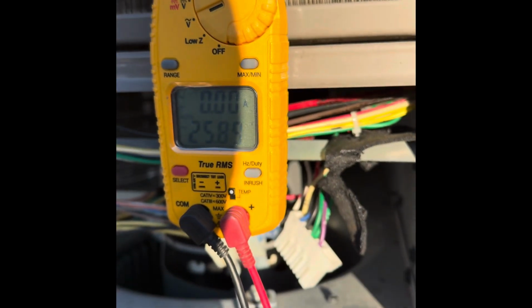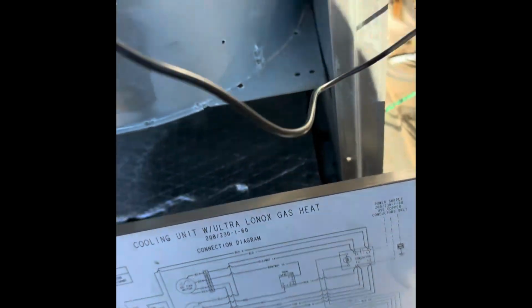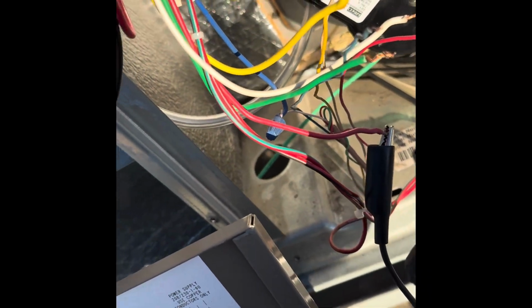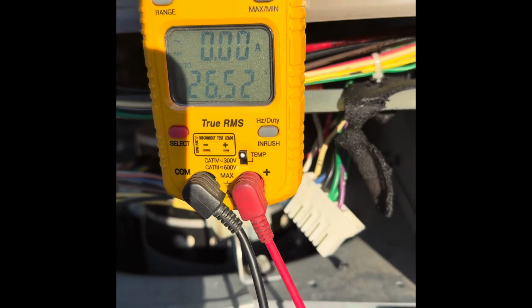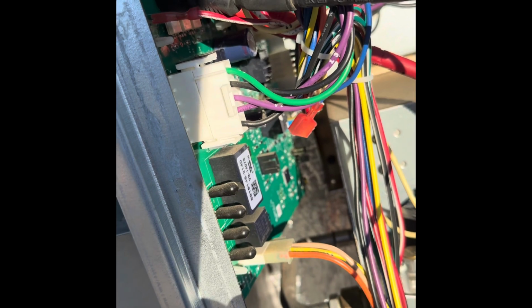And then we're going to check the heating and the fan side. Okay, so we're going to check the fan side here. You're going to use the little jumper, put it here. 24 volts. All right, so now we know that we do have voltage coming from the control board signaling the motor to turn on.